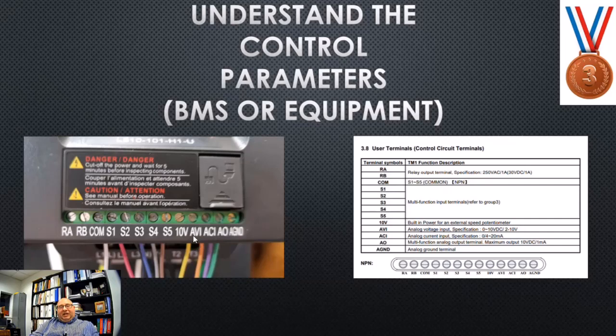AVI stands for analog voltage input. This is where we would do a 0 to 10 volt speed reference signal going into the drive. You have an analog current input, ACI, which would be for a 4 to 20 input for a speed control reference. You have an analog output, so you could actually use that for status, or if you want to do it for fan tracking, you could go in this drive as an input.